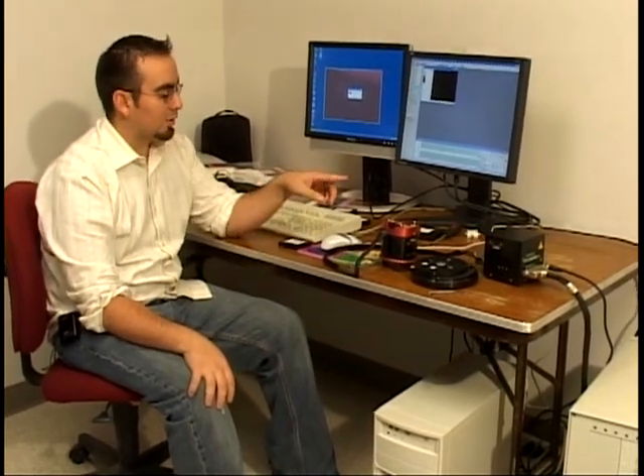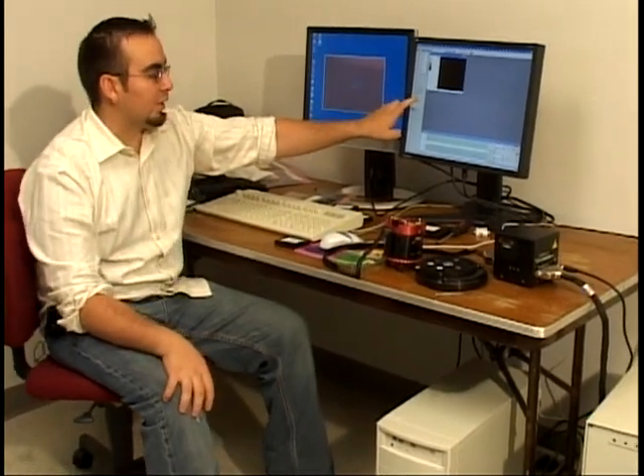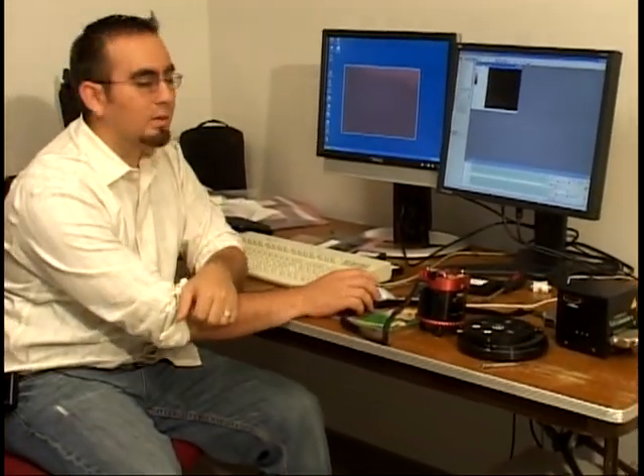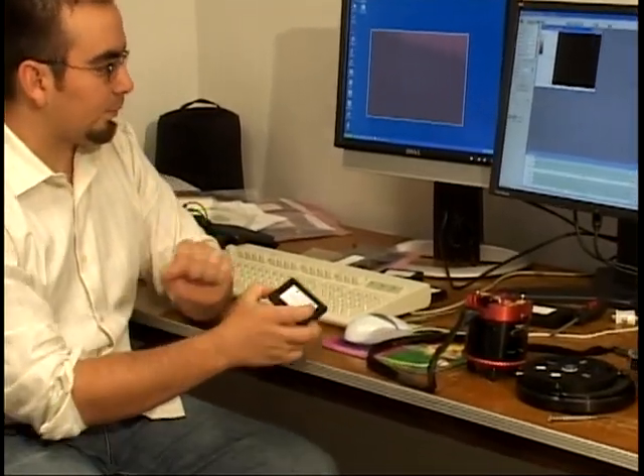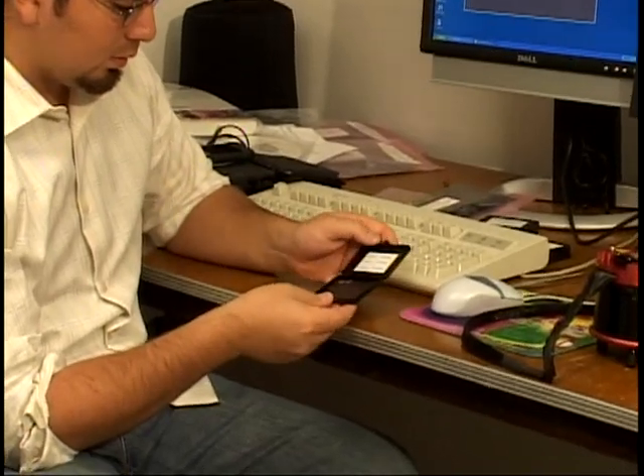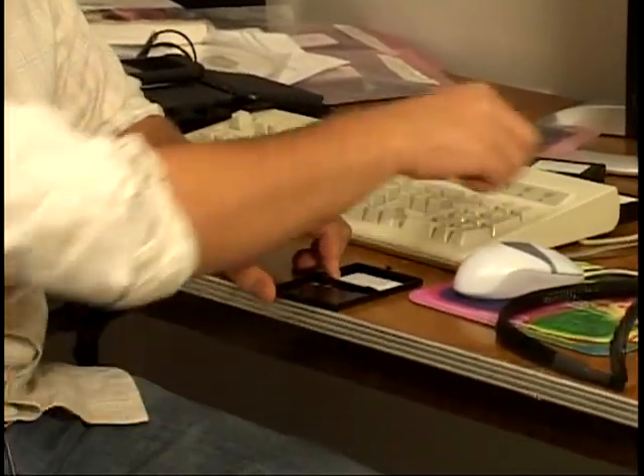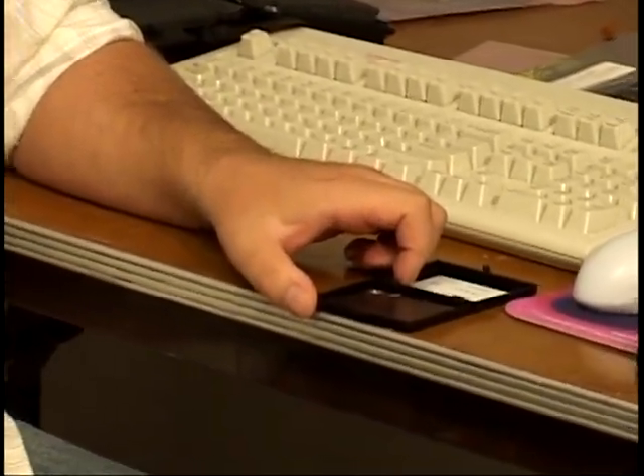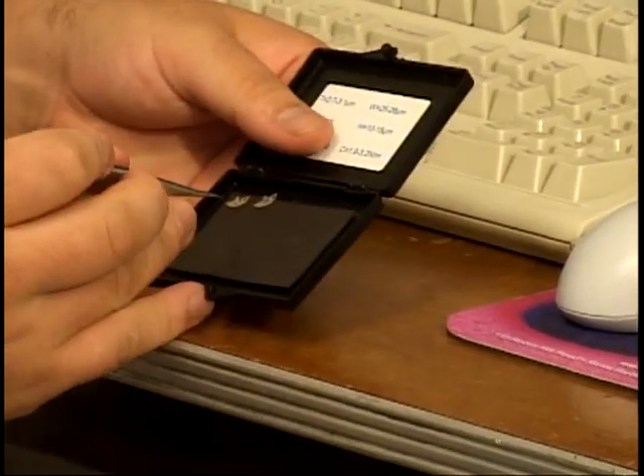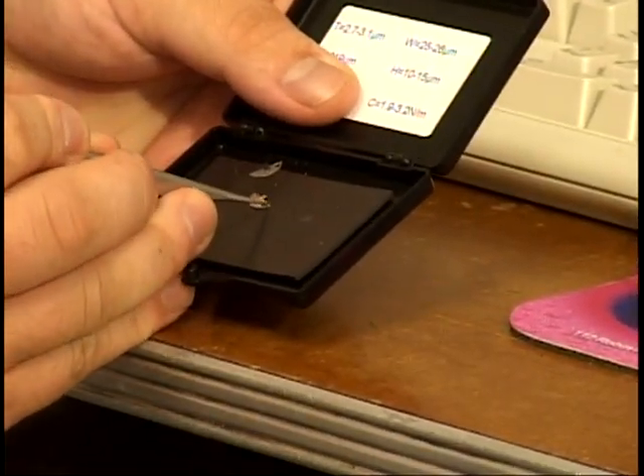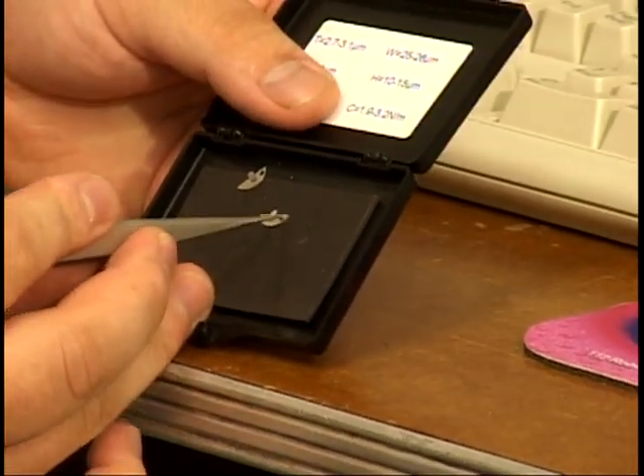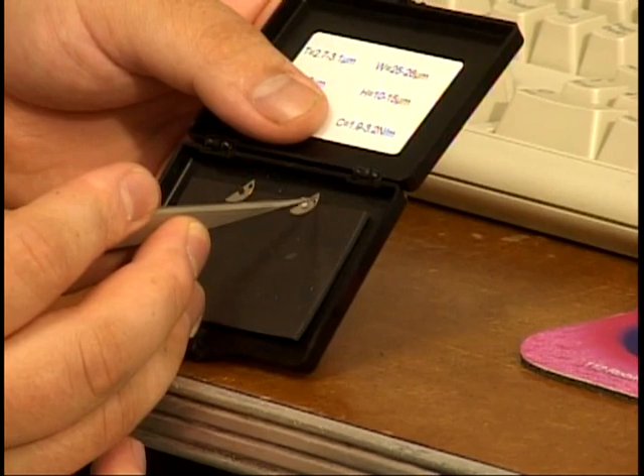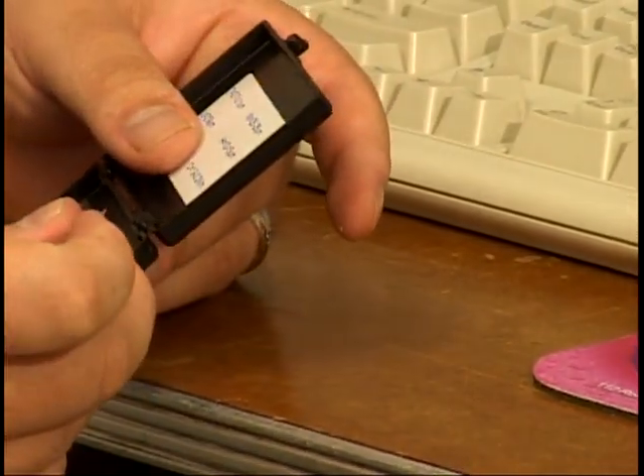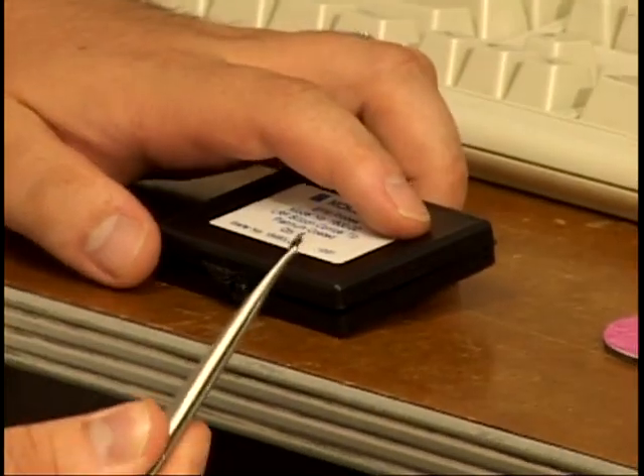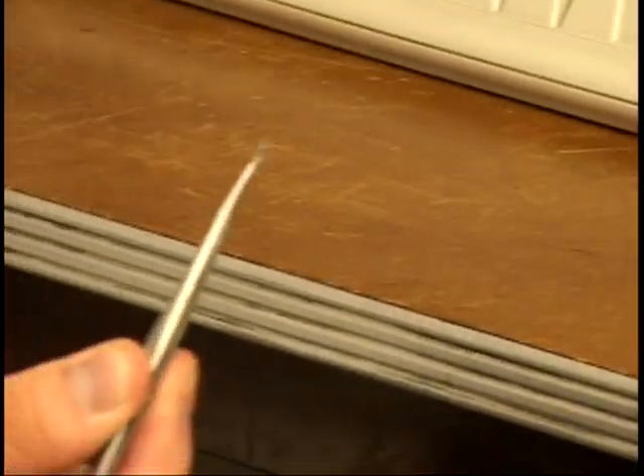And if the laser is on, turn it off using the laser off button right here on the screen, which it was. We're going to use the probe. I don't know if you want to get closer on this one. So these half moon pre-mounted probes have a hole in them, so you can drag them across all the way to the edge, so you can pull it off this magnet. Hold it from one side. Close your box up again. That way you keep any kind of dust or anything off the probes.